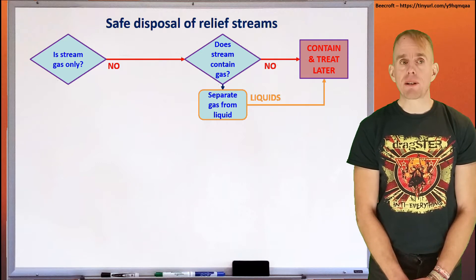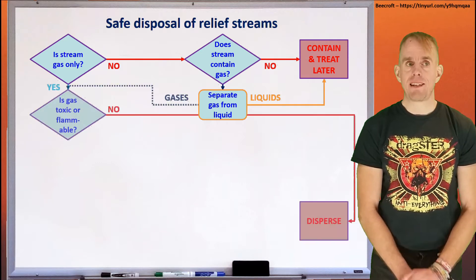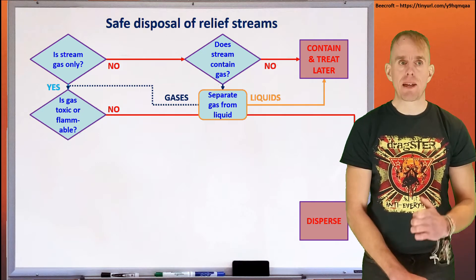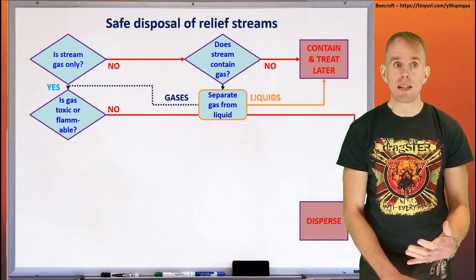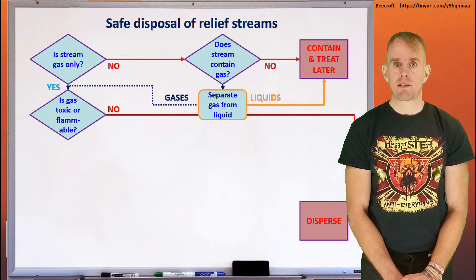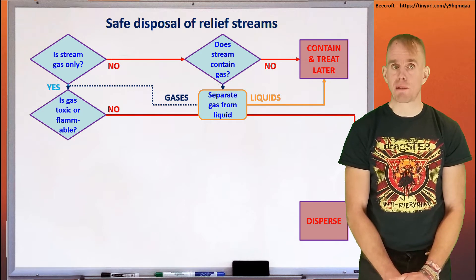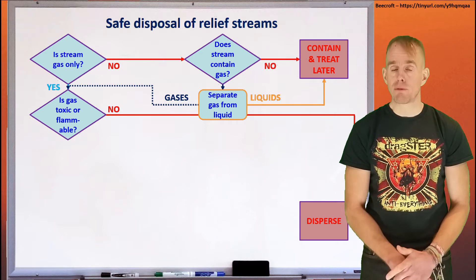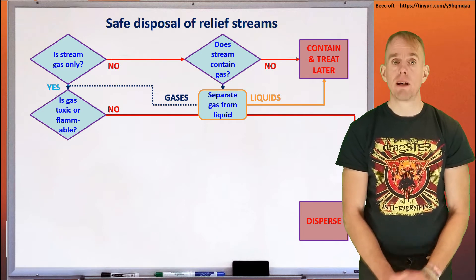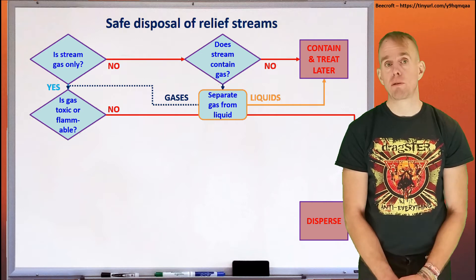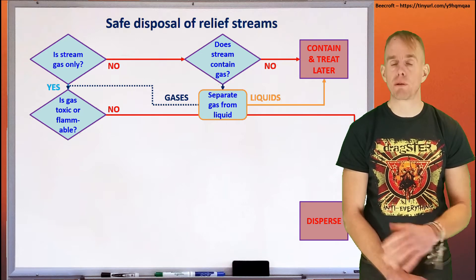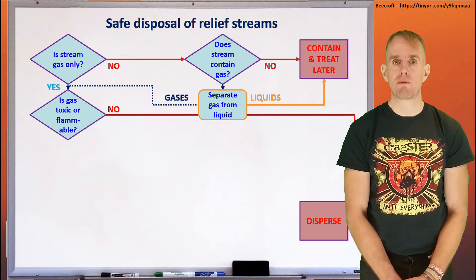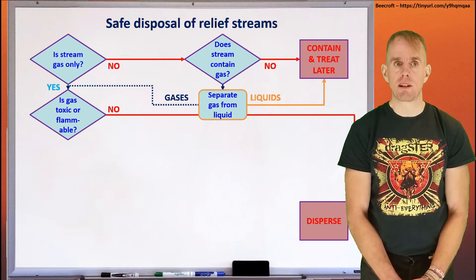If we've got gas in our relief stream, then we make sure that the relief stream contains only gas. And then we ask ourselves the question: is the gas either toxic or flammable? If not, the answer is an easy one — disperse to atmosphere through a relief valve or through a bursting disk. We'll see pictures of relief valves that do this in a second.